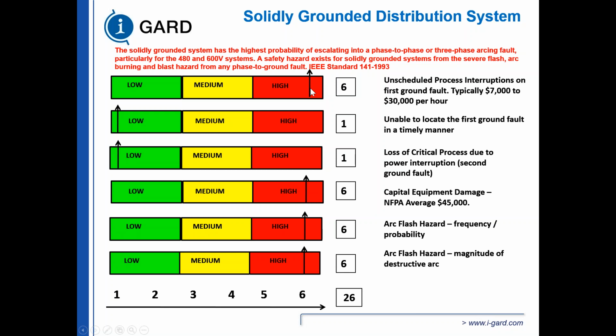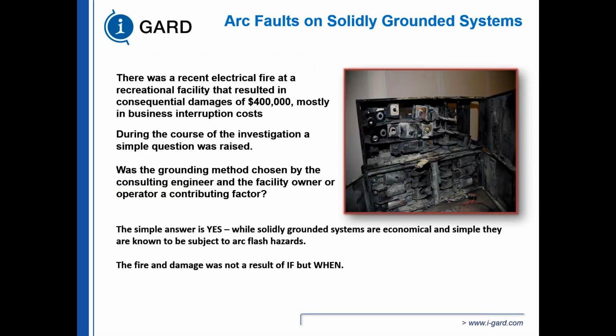Both the NEC and the CEC dictate that if you have a system that's greater than 150 volts to ground, greater than 1,000 amps, you must have ground fault protection. So to meet the minimum code requirement, we put ground fault protection on the main breaker. That example we saw here had a 600 volt switch with ground fault protection and fuses everywhere else after that. So the only place you could put ground fault protection was on the main isolation device.